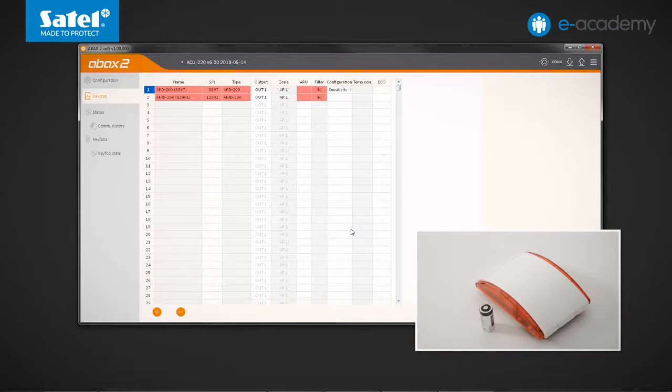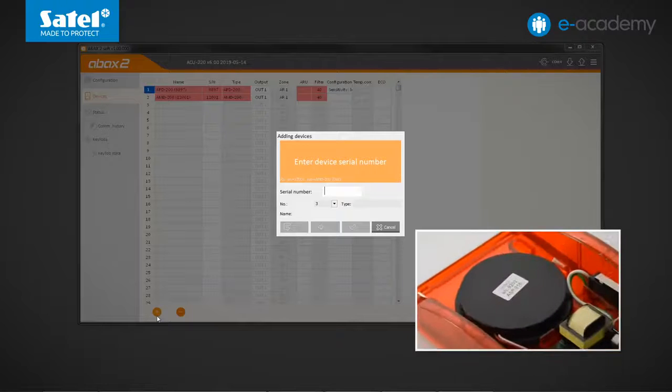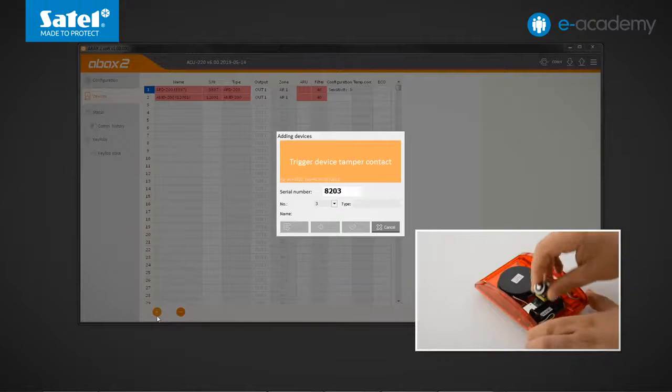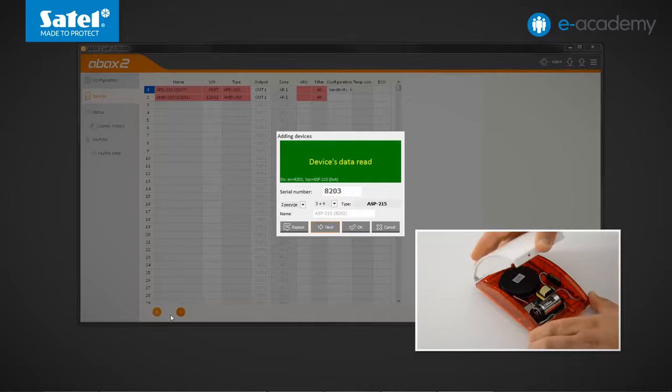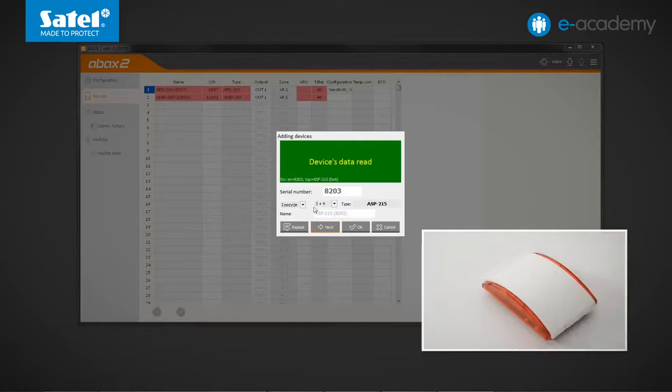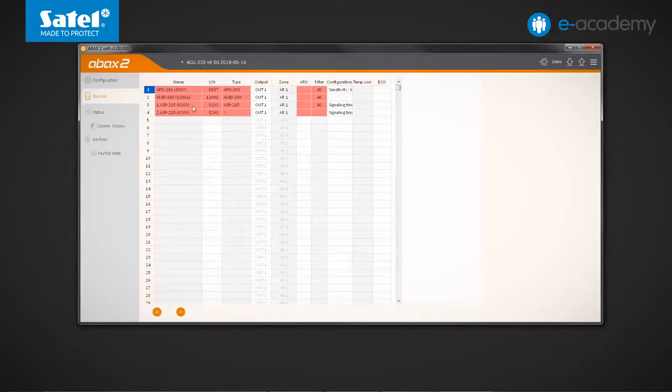Another device to be registered to the controller will be the ASP215 indoor acoustic optical siren. Click the plus button. Open the device enclosure. Find the serial number and enter it in the program. Violate the tamper switch or insert battery in the siren battery compartment. Device data has been loaded. We can close the enclosure. The ASP215 takes up two positions. Therefore, the program prompts us to use two of the available numbers. Click OK. The siren has appeared on the list. It occupies two rows in the table. After registering the devices, click on the send data button.